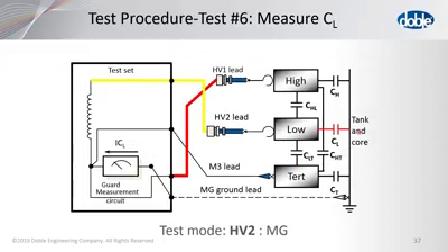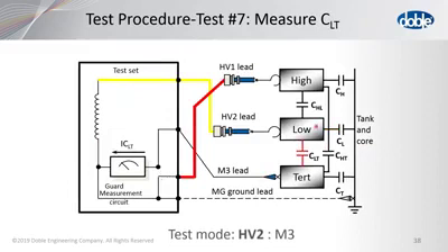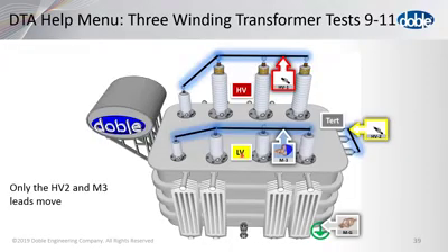Number 6, it only measures the CL, right? And notice that the CLT is not being measured. And then the last one, the CLT is measured, you energize here, and you measure the tertiary. All right, now you do have to move the leads for tests 9 through 11. And what you do is you switch these 2 leads.